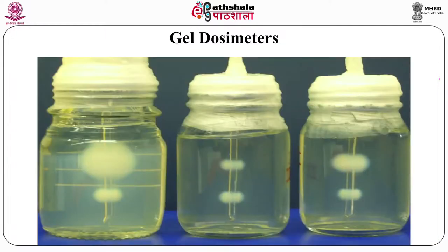Until now we were discussing point dosimeters or 2D dosimeters. A new class of dosimeters under active research are gel dosimeters, which can be used for mapping three-dimensional doses because the dose information is trapped in three dimensions within the gel. If you can read this information — for example, ferrous being converted into ferric in a gel matrix — using imaging methodology like MRI or CT to measure ferric concentration, you can map the dose in three dimensions.